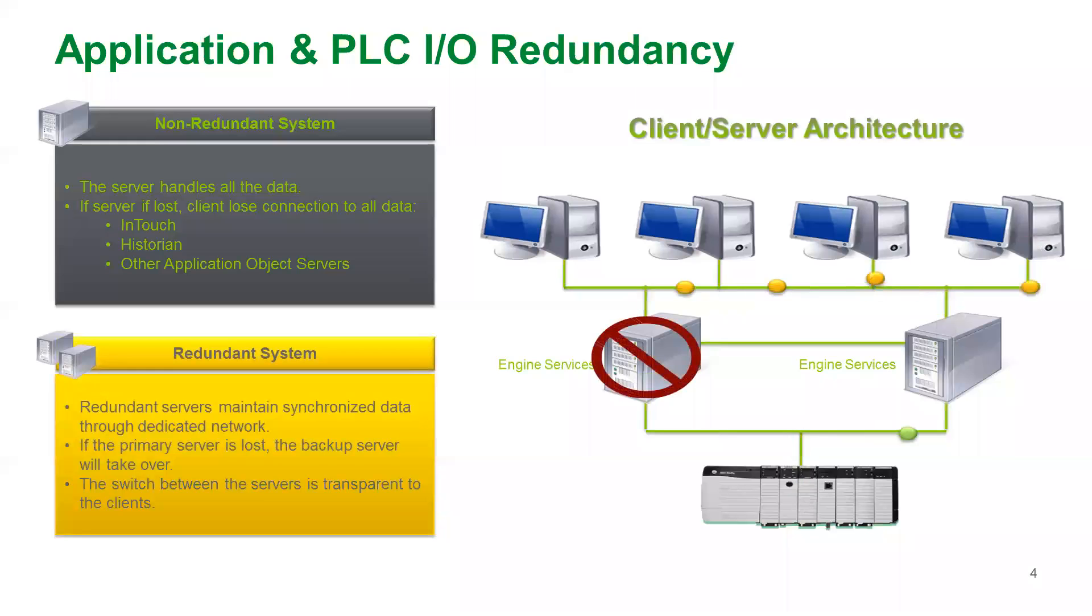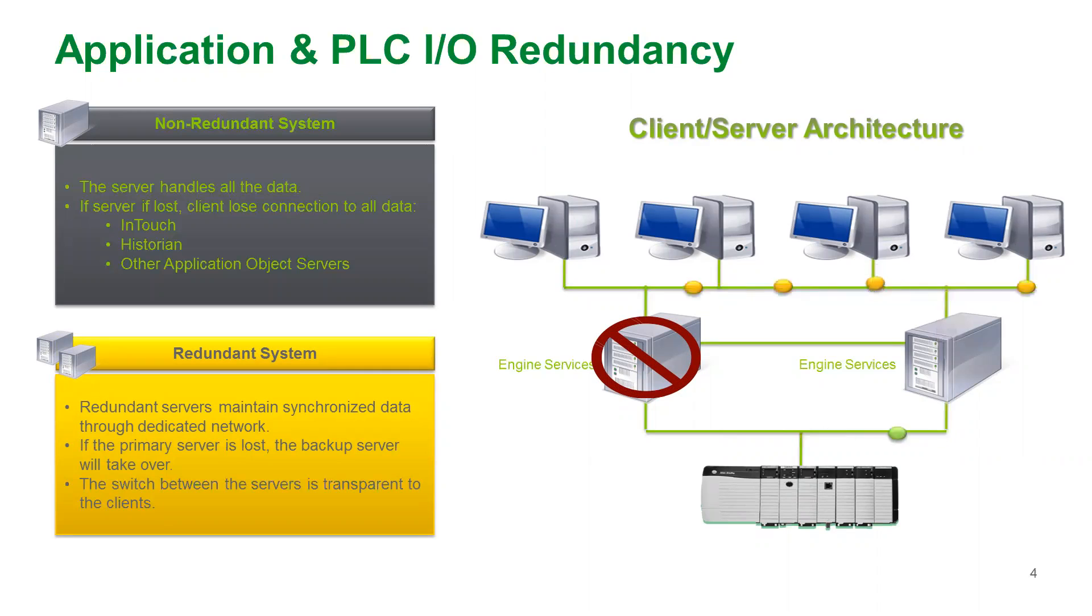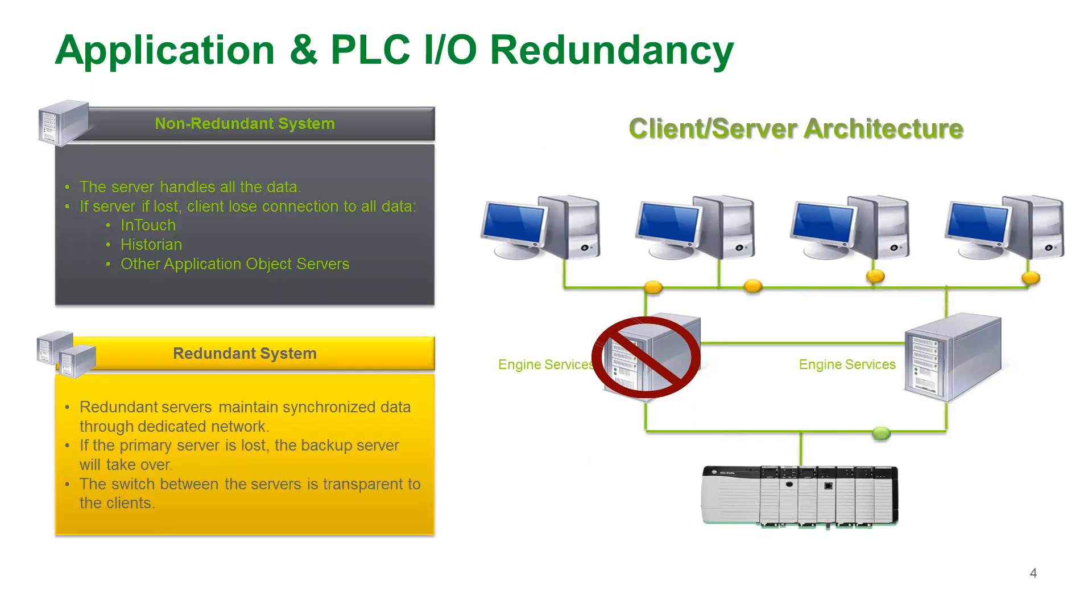Engines can be made to be a redundant pair and they monitor each other with a dedicated network called a redundant message channel. If a standby engine partner detects there's a problem with its partner, that automatically becomes the active engine.